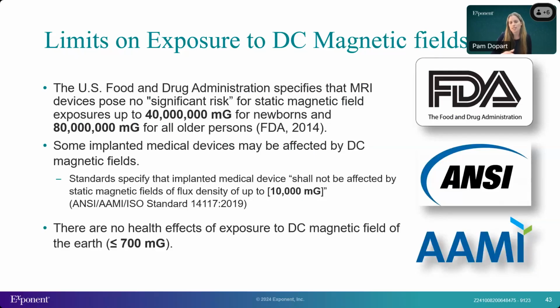For DC fields, some exposure limits have been developed based on extensive research in specific areas. For example, the US Food and Drug Administration has limits for static magnetic fields in MRI machines. In addition, some implanted medical devices, such as pacemakers, can be affected by DC magnetic fields. This has resulted in some standard setting organizations developing protective standards, requiring that such medical devices not be affected by static magnetic fields up to a certain exposure level.